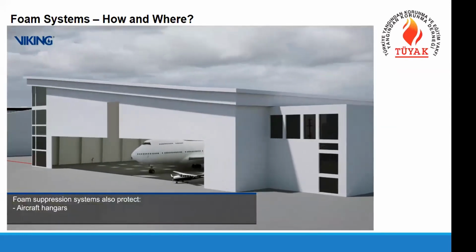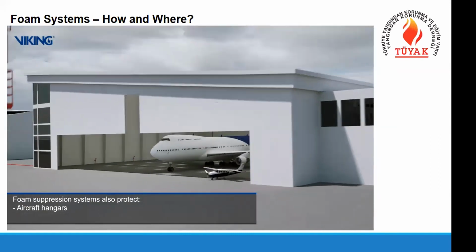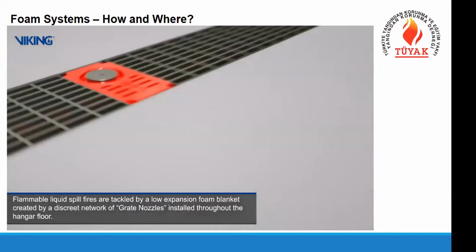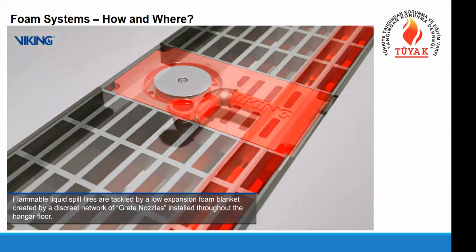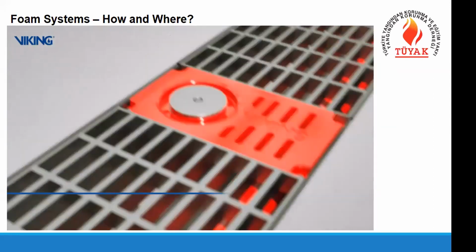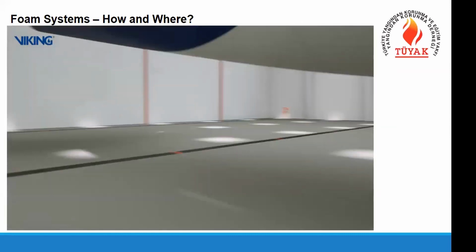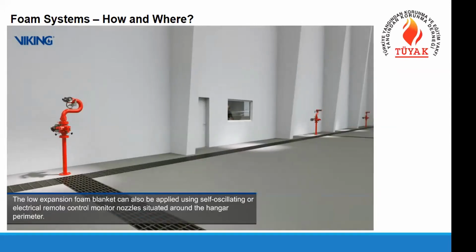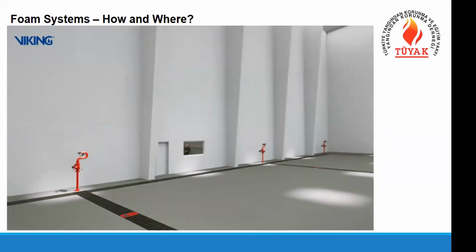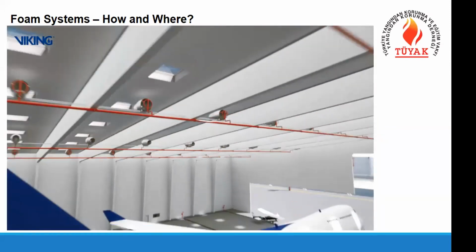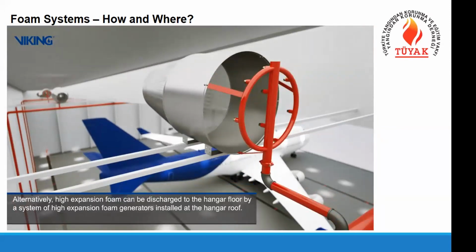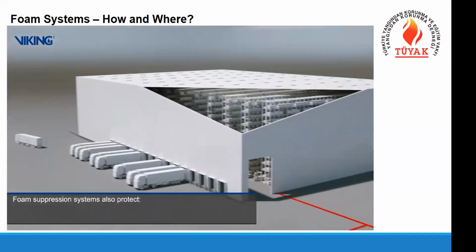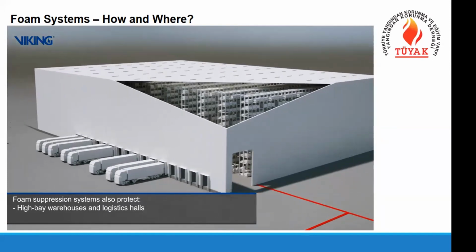In aircraft hangars, we have different types of systems on floor level. We have grate nozzles integrated into the floor of the hangar that eliminate any kind of flammable and jet fuel spill fires and control the fire in a very fast manner. We can also use monitors in the hangars. These are automatically oscillating monitors like we have in the fields for watering the plants, but for fire protection. For hangar protection, we also have high expansion systems that expand the foam to almost 1,000 times its original volume, so it fills up some height in the hangar or in the storage rooms.